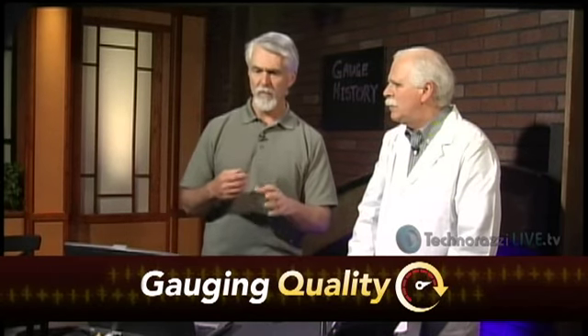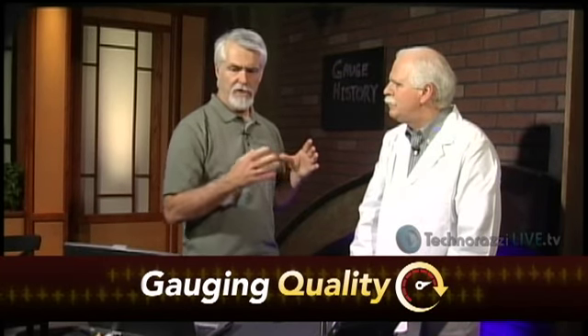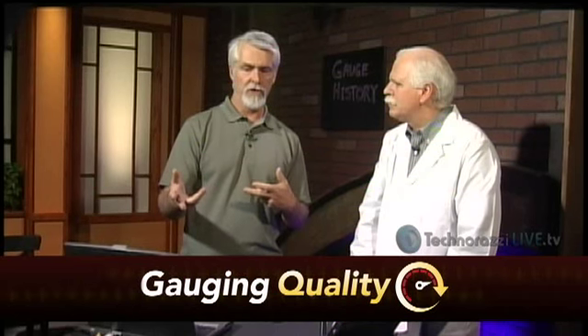Usually there will be an interval that will trigger a calibration event. Sometimes there will be an incident, somebody has dropped it, things of that nature. But that would apply a lot in stability, linearity. Matter of fact, we don't have a way to show it here. I've seen it in other slides. You can get basically a control chart on the gauges that allows you to look at your gauge from a statistical point of view, see what's going on, and see if there are any special events. That's very valid.